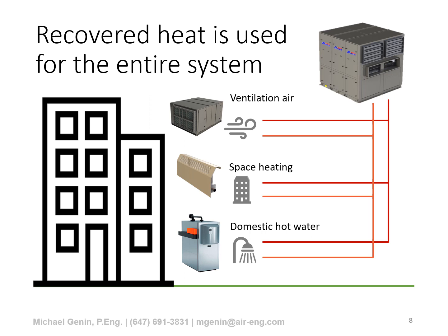So this means that our ventilation system and the heat recovered from it can now be used to offset carbon emissions in other parts of the building. And because active heat recovery can extract so much more heat using the compressor, we're going to have excess heat left over from the ventilation that can then be used to contribute space heating and domestic hot water. And as it becomes more mild outside, we're going to have even more surplus heat available from this machine to further contribute and offload the carbon emissions from our base building heating system.